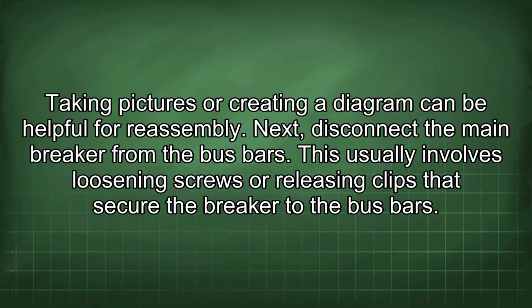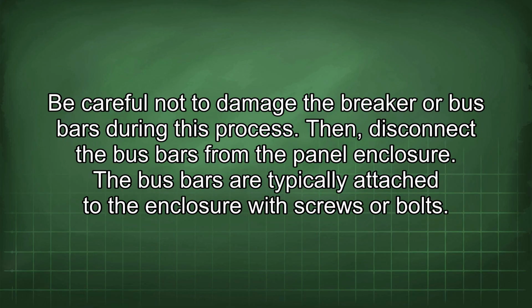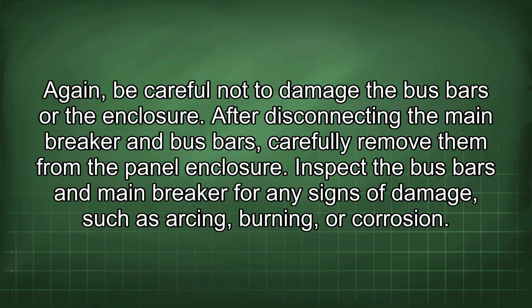Next, disconnect the main breaker from the bus bars. This usually involves loosening screws or releasing clips that secure the breaker to the bus bars. Be careful not to damage the breaker or bus bars during this process. Then, disconnect the bus bars from the panel enclosure. The bus bars are typically attached to the enclosure with screws or bolts. Again, be careful not to damage the bus bars or the enclosure. After disconnecting the main breaker and bus bars, carefully remove them from the panel enclosure.